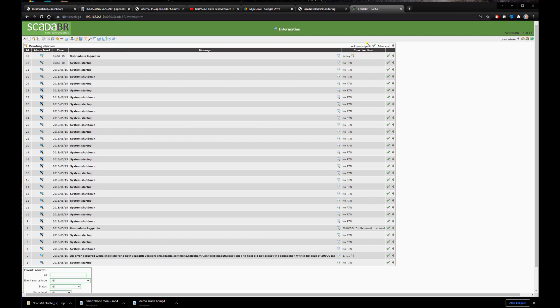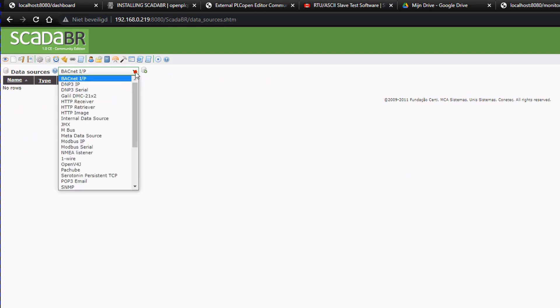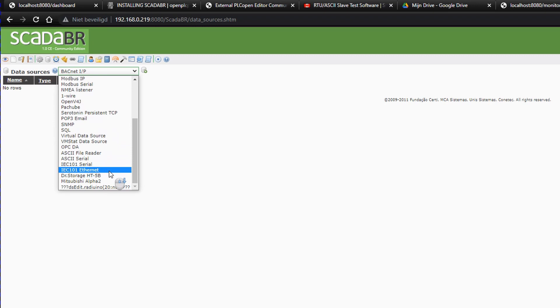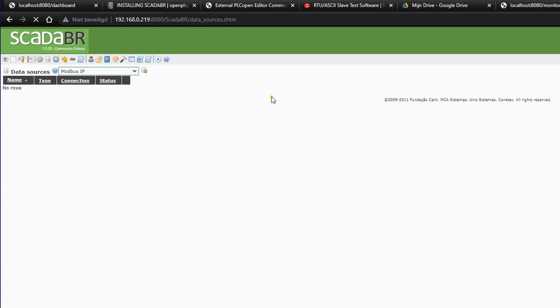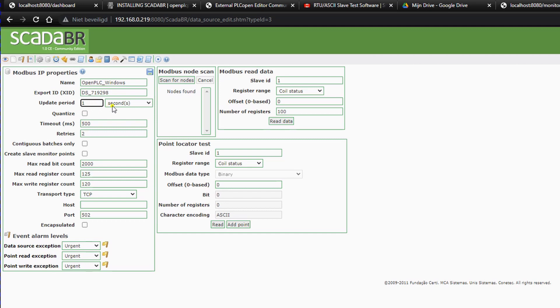We select Modbus IP and add a data source. We will give it the name 'OpenPLC on Windows', change the update period to 500 milliseconds so it's more or less real time, set the timeout to one second, and it's important the transport type is set to TCP with Keep Alive.